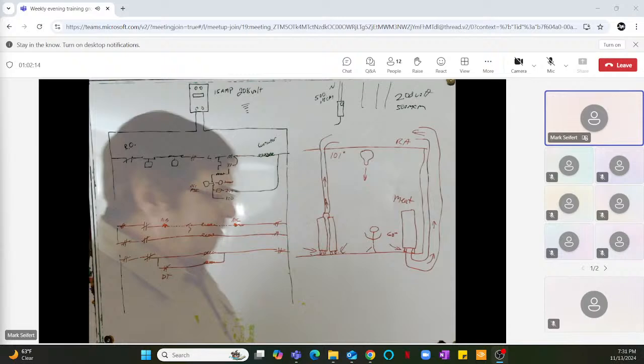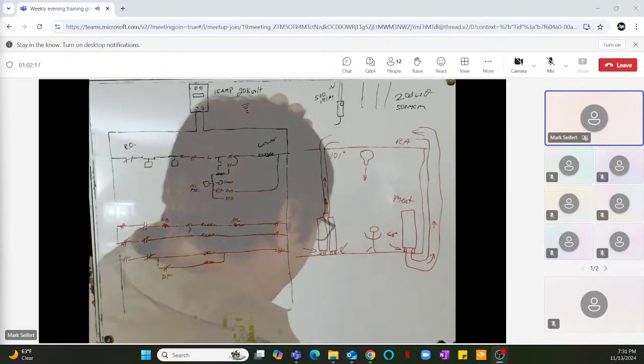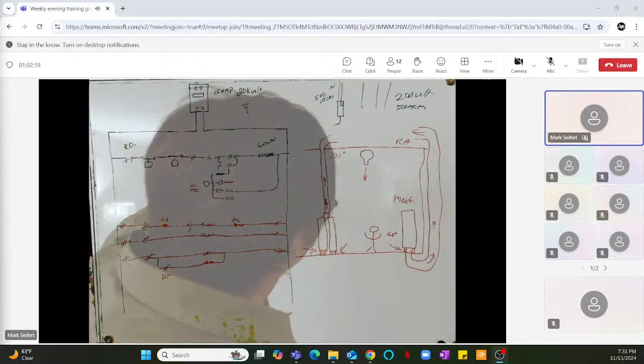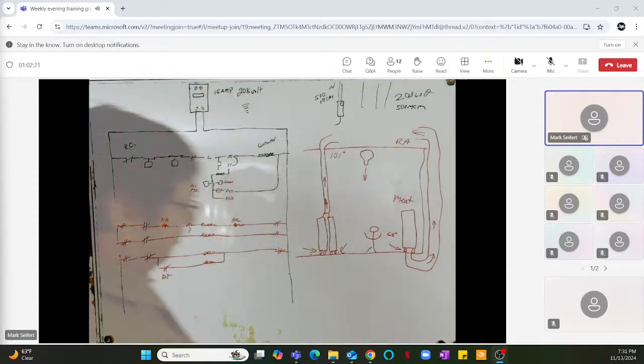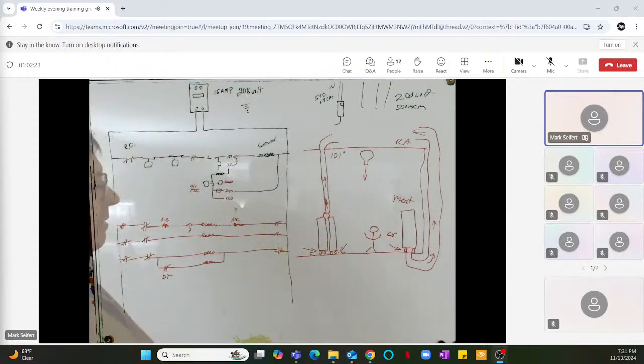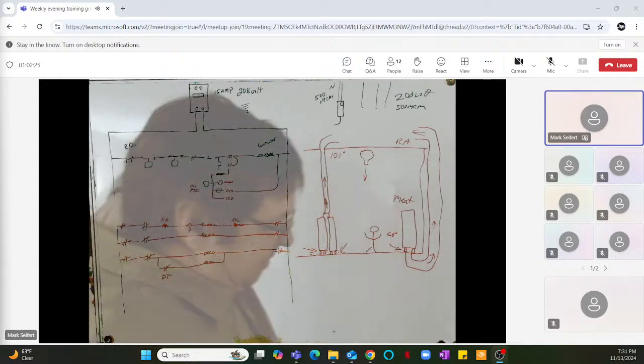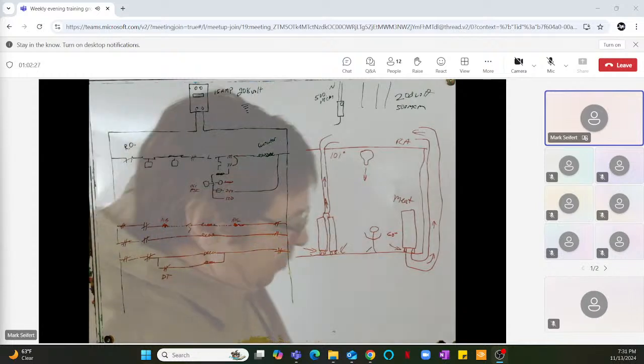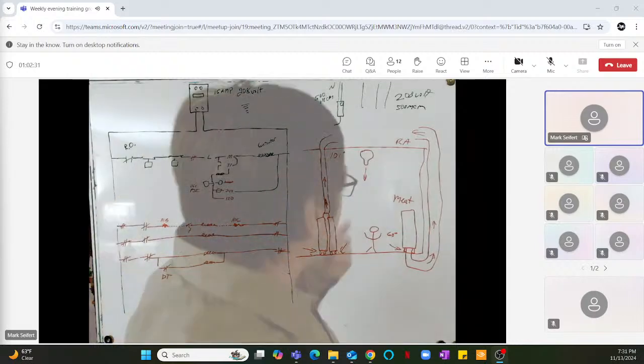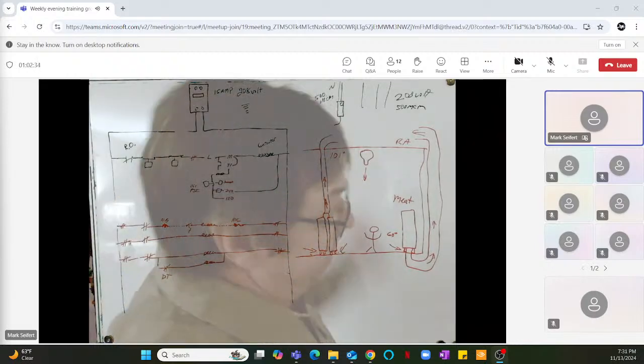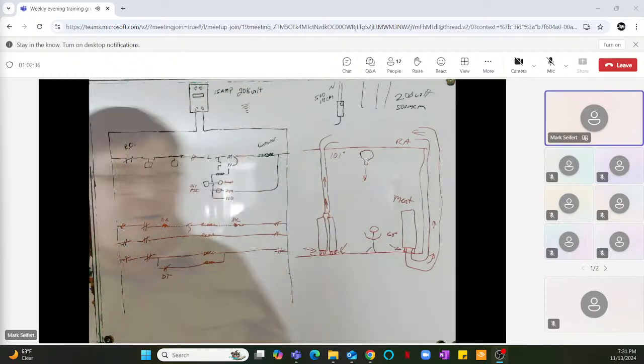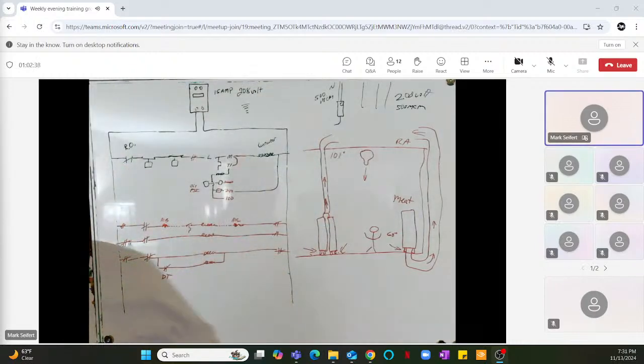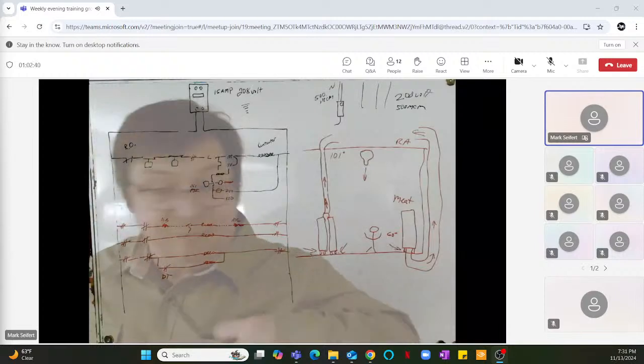Yeah, now's the time to start looking into this, guys. It hasn't been real bad with the calls. Call loads have been pretty low. But let's get the store's heating working. If we don't do it now, and we do have a heat exchanger that's rusted out, cracked, or whatever, we're not going to be able to get a new one in until probably January. And that's if we're rushing it.